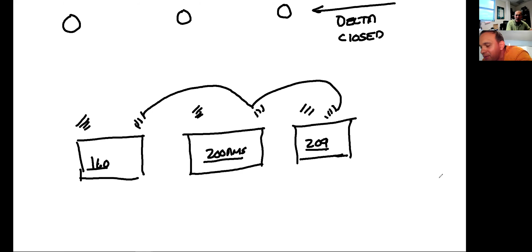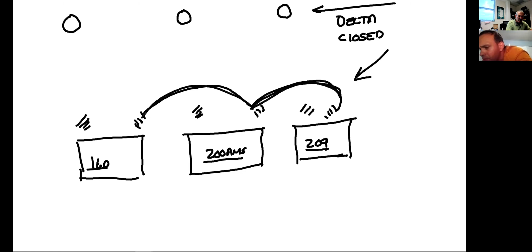Where does unbalanced load go when I do have a neutral? Goes back up the neutral. Well, I don't have a neutral in closed delta. Where does unbalanced flow go then? When I have a floating neutral, where does it go when I don't have a neutral to use? What's interconnected? The floating neutral -- it's interconnected to all 3 transformers. This is what we call load sharing.